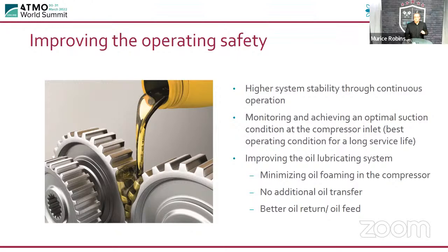So it doesn't matter how the system is running or what condition it's running in. Your oil is always being separated. It's always going to the right position. There's no foaming in the compressors. There's no oil transfer, and you have a much better oil return and oil feed.